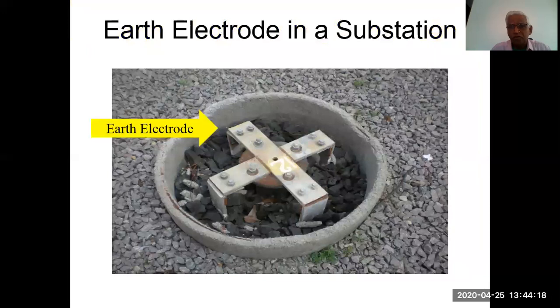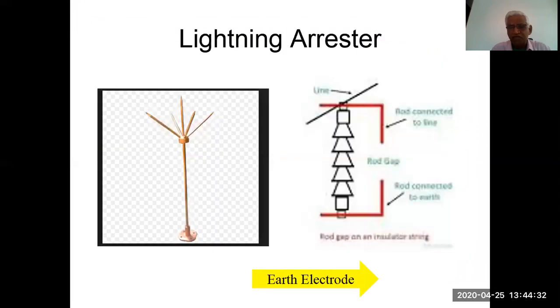Now, this is an earth electrode in a substation, and you have seen the earthing electrode also. And this is a nice way of doing it. This has to take care of the short circuit level of the substation. And this is the lightning arrestor. The left side one is generally kept on the top of the building, so lightning is diverted to the ground. Lightning cannot be avoided. It's not in our hands. It can be diverted to the ground. The right side one is similar, but this can be used with transformers or electrical equipment.